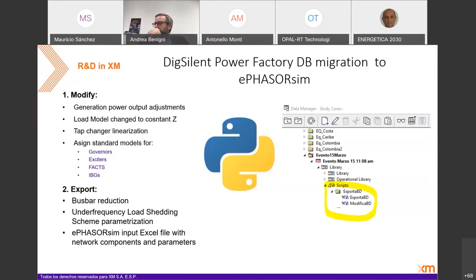Once this script has run, we run another script that automatically exports all the components and reads all the parameters, does the bus reduction for the substations that are modeled in great detail in DigSilent. We convert these substations into a single bus bar in the phasor sim model. We also migrate the parameters of the load shedding, the frequency load shedding scheme, and set all these parameters in the new tool, the phasor sim. Finally, this script produces or populates the Excel sheet, which is the main input file to begin a real-time simulation.